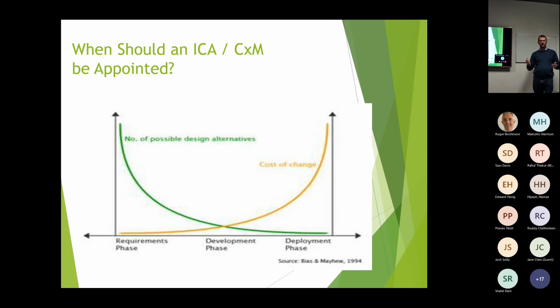Once you're on site and the architect turns around and says, there's no way you're putting access hatches in that ceiling, and you go, well, I've got all these dampers to get to, they say, well, that's your tough luck. Okay, so what do we do? Guess what they should be set to, and then when the ceiling goes up, it's doing what it's doing, or do we leave a small child up there to adjust them when we need to? There's various options, but obviously trying to do it earlier is the key.